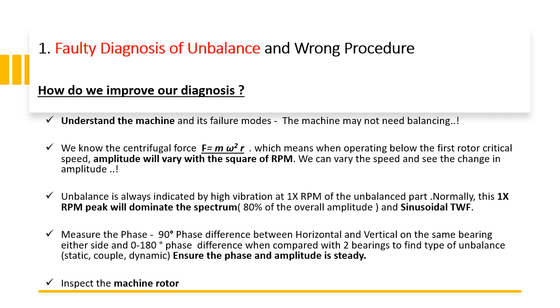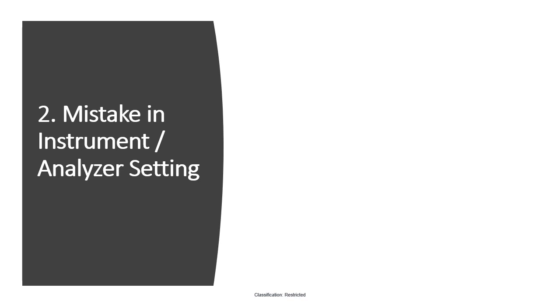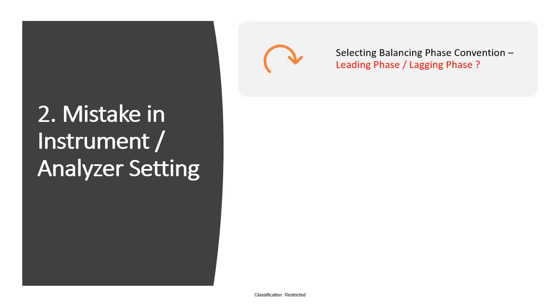The second mistake involves instrument or analyzer settings. First, selecting the wrong balancing phase convention — each analyzer has a setting for whether phase is leading or lagging, which determines weight location with respect to the direction of rotation. Most analyzers default to lagging phase, which gives a positive phase angle where angles increase in the opposite direction to rotation.